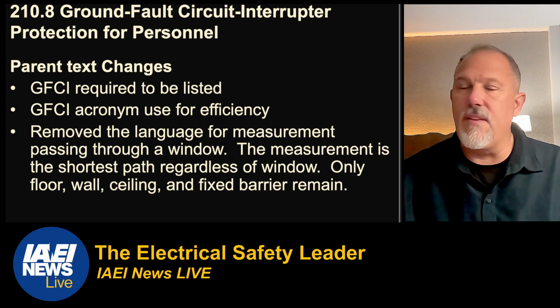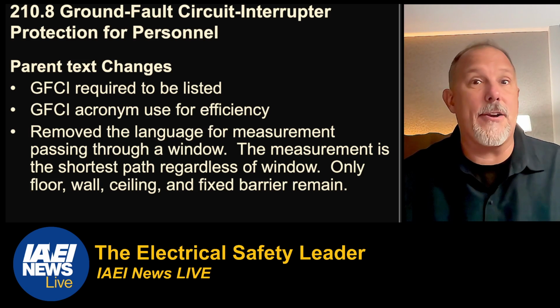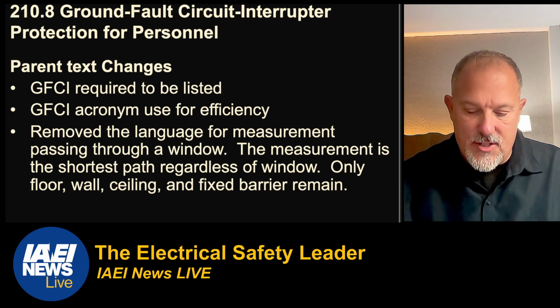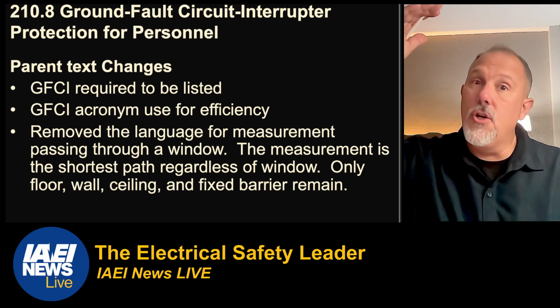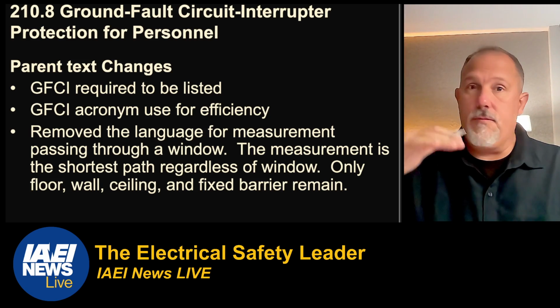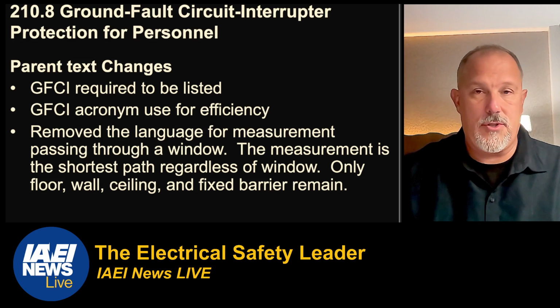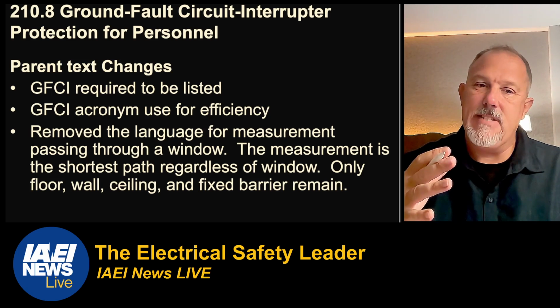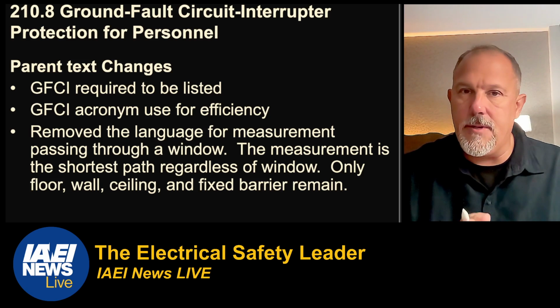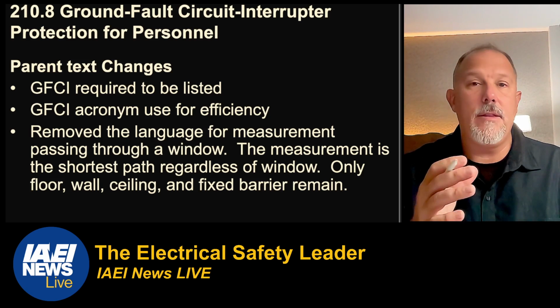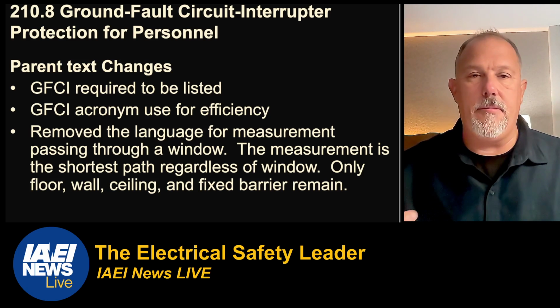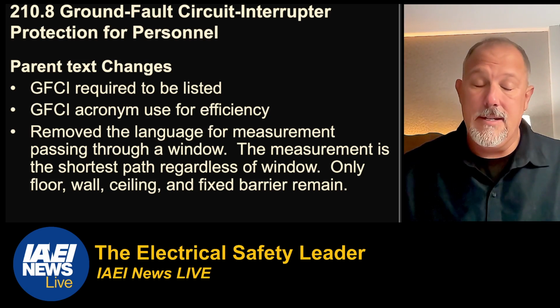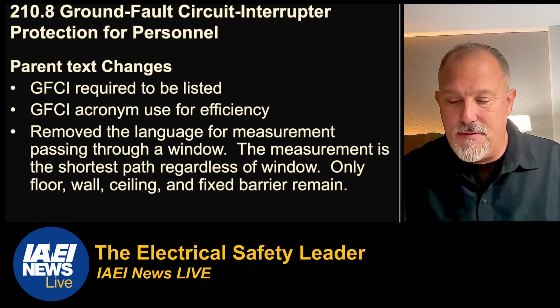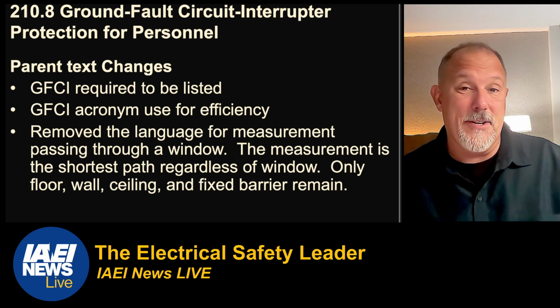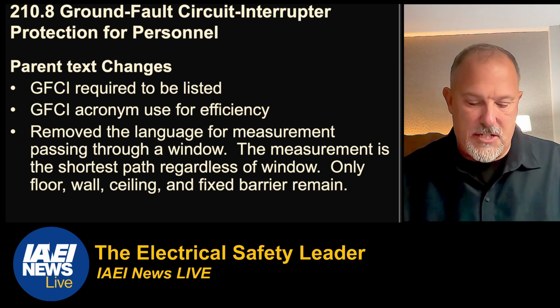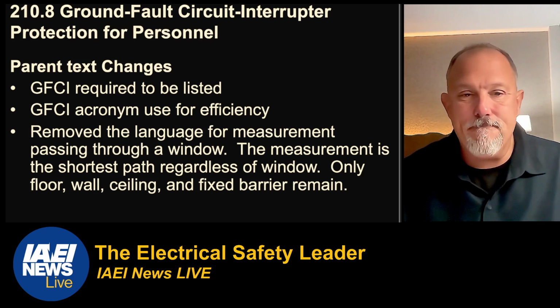I think it was Article 625. I can't remember which article I was looking at. There was an acronym they were using, and I'm like, what is that acronym? And I had to go up through the code section, through the whole article to find the first use. So just, again, be mindful that if there's an acronym in the code, you may see an acronym and wonder, well, it's not defined. What does that acronym mean? You may have to search for it, unfortunately. So maybe that's the power of NFPA Link. I don't know, but and the whole online experience. But just be mindful of that.